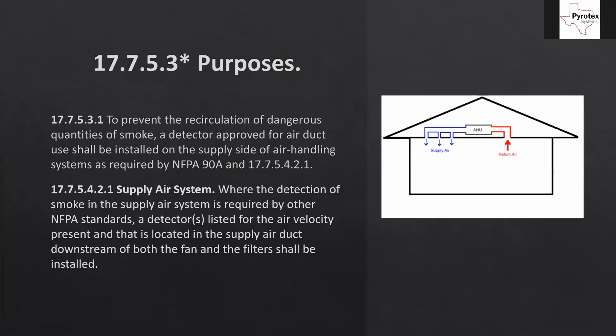The purpose of duct detectors is to prevent the recirculation of dangerous quantities of smoke. A detector approved for air duct use shall be installed on the supply side of an air handling system as required by NFPA 90A. Per section 17.7.5.4.2.1: when detection of smoke in the supply air system is required by other NFPA standards, a detector listed for the air velocity present, located in the supply air duct downstream of both the fan and the filter, shall be installed. This is basically all the 72 tells us.